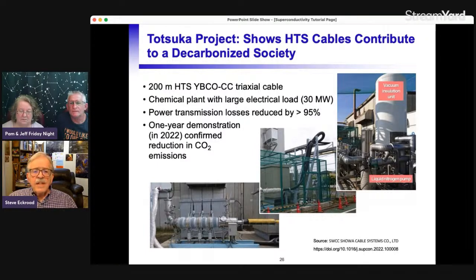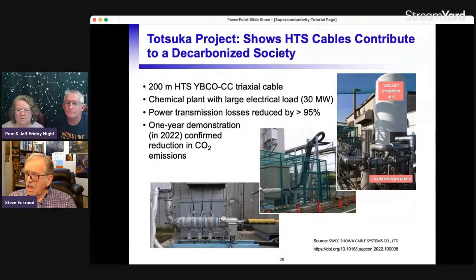The picture on the lower left is the termination of the cable. When you come to the end of the cable, you've got to transition across three things: from high voltage, in this case maybe 23 kilovolts, to ground, so you need something that can stand off that much voltage. You have to go from vacuum to atmosphere, and from liquid nitrogen temperatures to room temperature. So it's a very complex piece of equipment called a termination, and you can see how complex it is there.